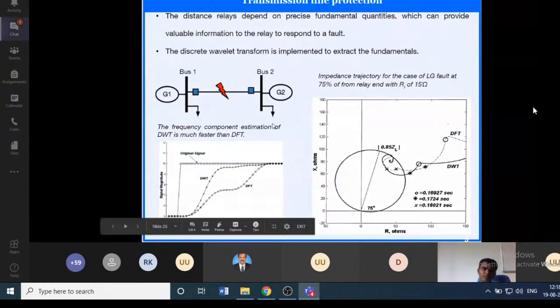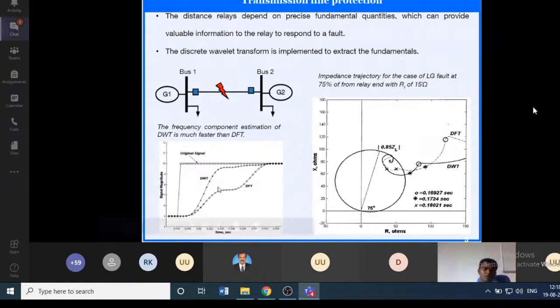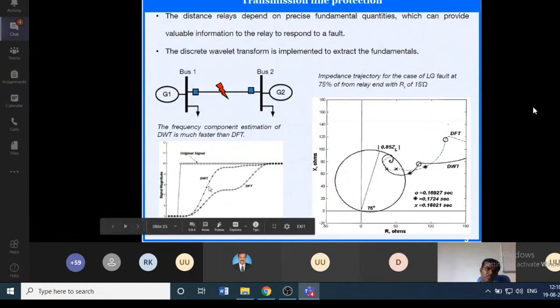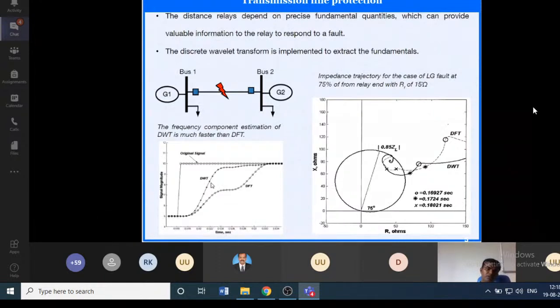Here we are going to see one example. This picture gives the comparison of discrete wavelet transform and discrete Fourier transform. Both are used to estimate the fundamental harmonics. When compared with DFT, the wavelet transform estimates the fundamental harmonics very quickly, so that it can help to isolate the fault quickly, so that we can isolate the faulty section before the critical clearing angle.